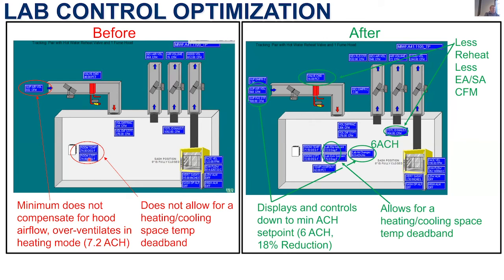So we relax that. And then on the supply side, it's going to track general exhaust with supply air, right? But the application is ignoring the hood exhaust. So the EH&S folks, or whatever you call that department, have worked with the engineering folks and said, okay, 6 air changes is what we want, but you're actually doing 7.2 air changes. So we're going to calculate the actual air changes, put it on the screen, and incorporate the lab exhaust. That's it.